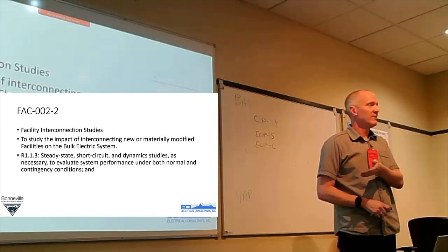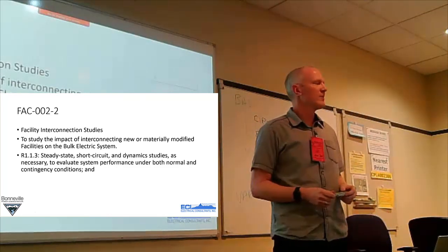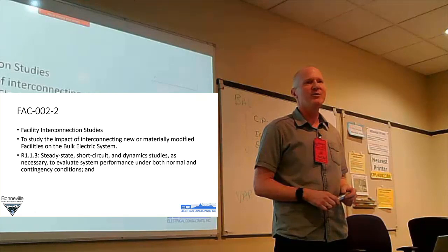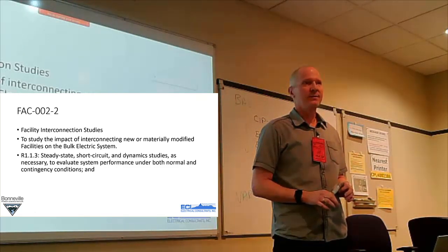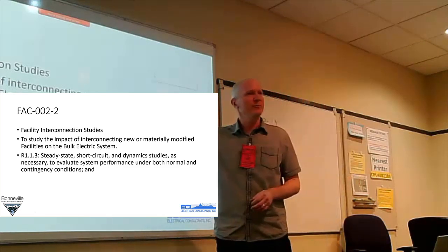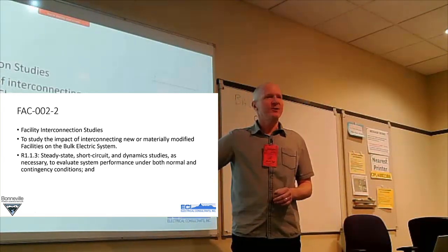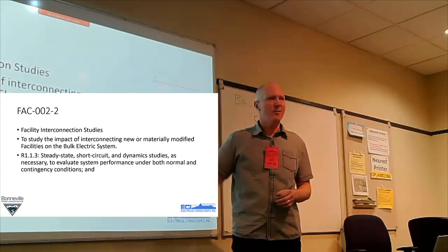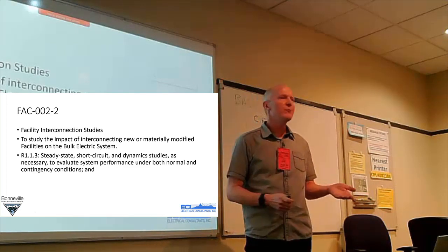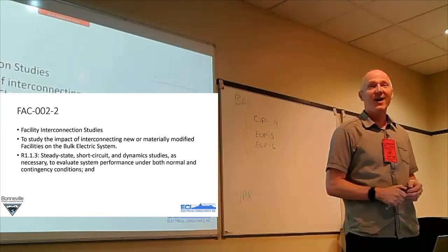Does that make sense? Now, you may not do it this way, but more than one other utility, sometimes their studies for a major project on the bulk electric system can be pretty light. And FAC-002 should warn you, no. You don't do a feasibility study when you're changing a station configuration, meaning you take a heavy summer case and run power flow on it and some list of P1 contingencies. You just don't do that, because your planner who's doing the assessment is going to find out.